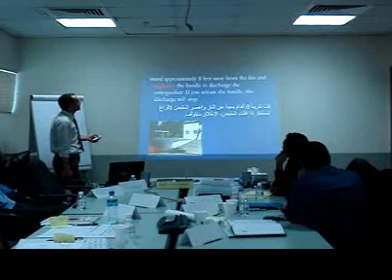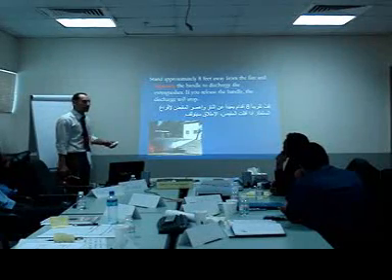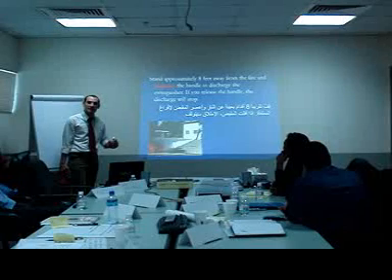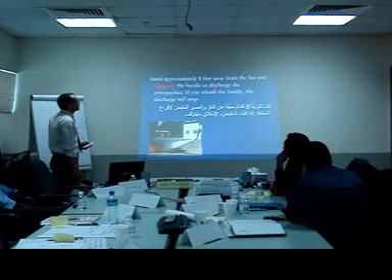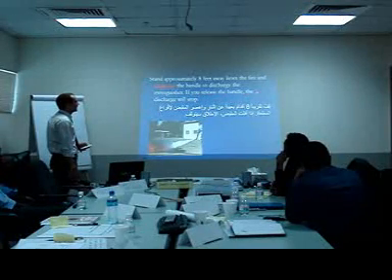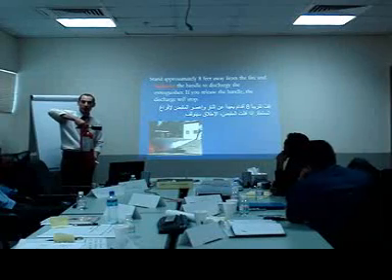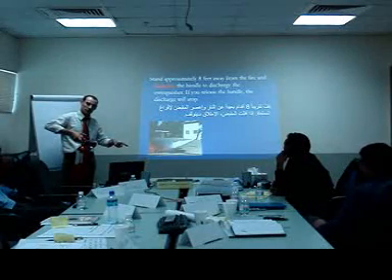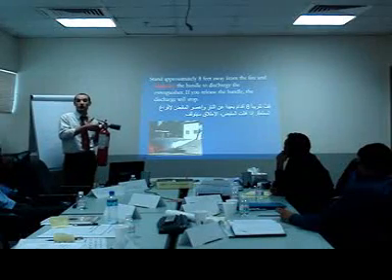Okay, stand approximately 8 feet away from the fire, around maybe 1.5 meters to 2 meters, just to remain safe. Squeeze the handle to discharge the extinguisher. If you release the handle, the discharge will stop. I mean, if you press this one, you will start discharging the extinguisher to fight the fire. If you release it, that's it, the extinguisher will stop.